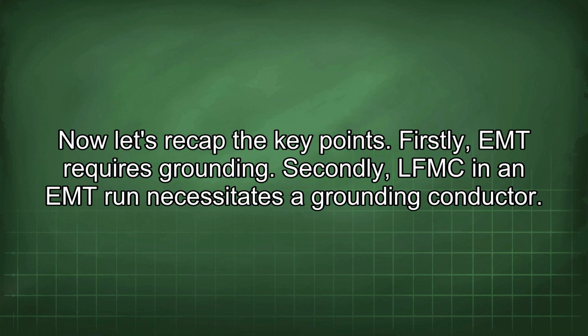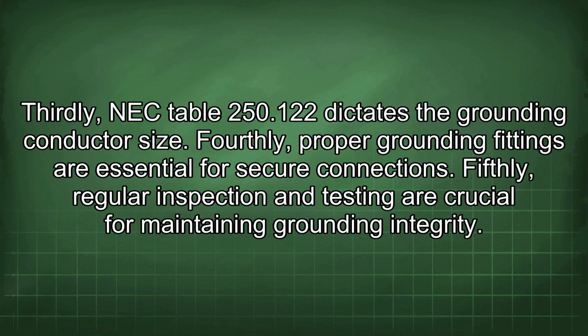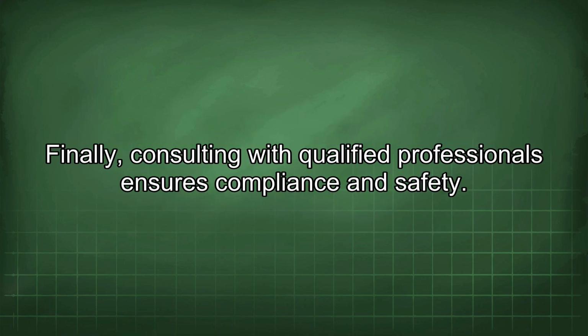Now let's recap the key points. Firstly, EMT requires grounding. Secondly, LFMC in an EMT run necessitates a grounding conductor. Thirdly, NEC Table 250.122 dictates the grounding conductor size. Fourthly, proper grounding fittings are essential for secure connections. Fifthly, regular inspection and testing are crucial for maintaining grounding integrity. Finally, consulting with qualified professionals ensures compliance and safety.